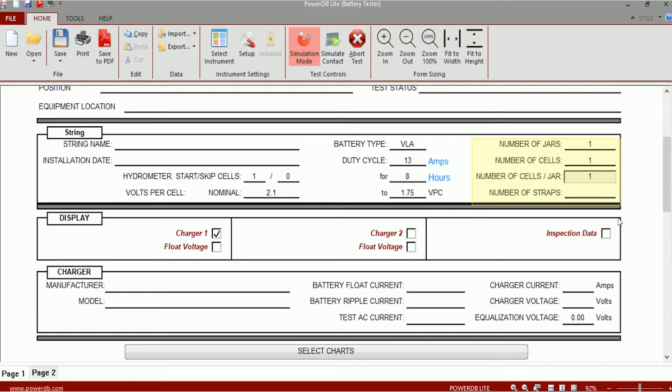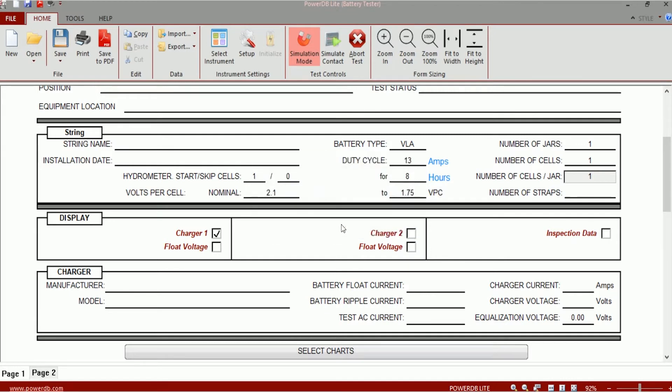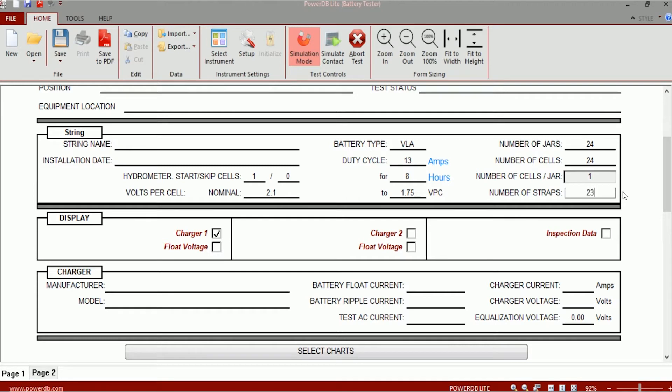This section gets populated when you download the impedance data from the instrument, but if you want to edit the values you can edit that. In what case would you need to edit the values? Let's say I ran the test on a 24 cell string. The way the data would look would be like this: I would be able to see number of jars, number of cells is 24, and it would say number of cells per jar is 1. The number of straps would be 24 or 23 depending on the instrument that you're using, and that can be edited as well.